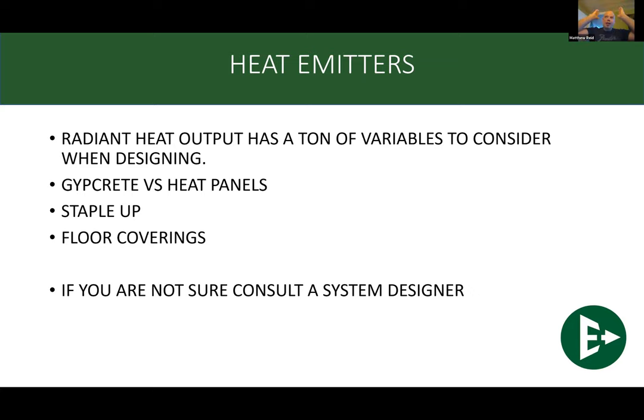It goes PEX into the subfloor, right against the subfloor, insulate it like crazy, as much as you possibly can. You can't insulate that one too much at all, and then put your ceiling up. This is also a good place when you're doing a staple up system in the joist spacing, where aluminum heat transfer panels are an extremely good idea. It's hard to drive heat through a staple up system.